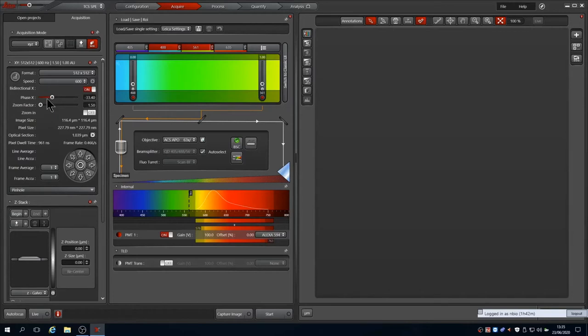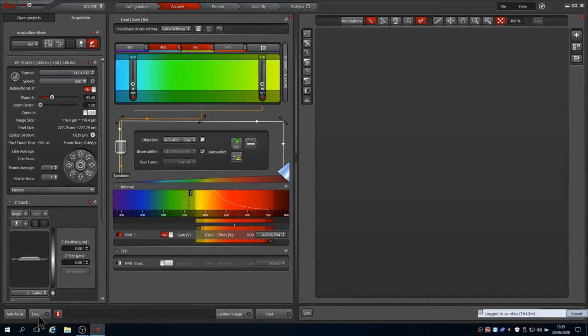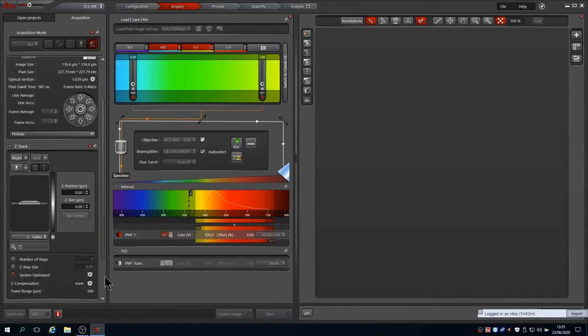We can increase the scan speed to 600 Hz with only a small increase in noise. Also, we can switch bi-directional scanning on to image on both sweeps of the galvo mirrors, as the alignment is quite good on this system. There are options for frame averaging or accumulation, but if we're setting the channels up we'll leave these off. Now we're ready to go live and start scanning the sample.